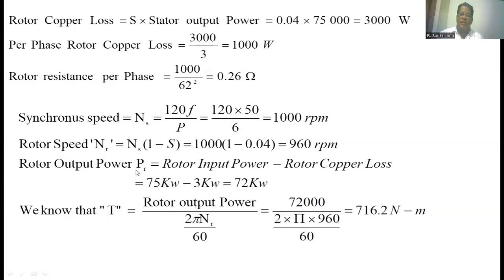The rotor output power equals rotor input power minus rotor copper loss. We already calculated the rotor copper loss as 3 kilowatts. So rotor output = 75 − 3 = 72 kilowatts (three-phase). The torque developed equals rotor output power divided by the angular velocity of the rotor: 2π × nr / 60. With rotor speed 960 rpm, we finally get 716.2 Nm.